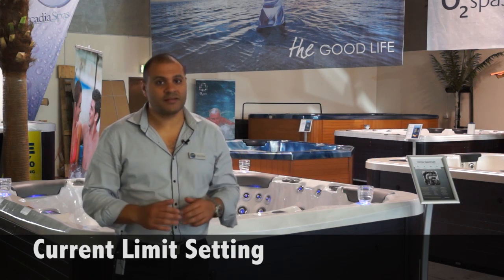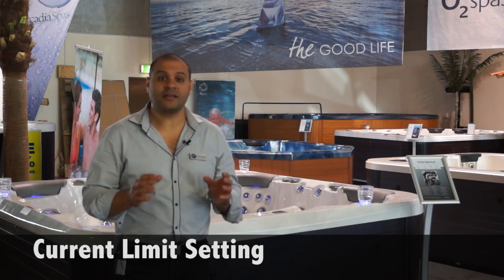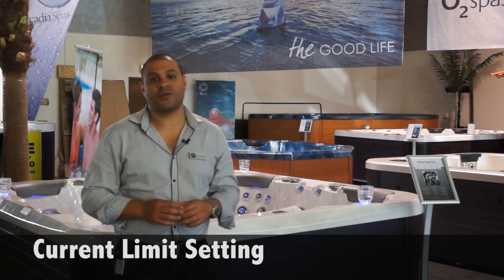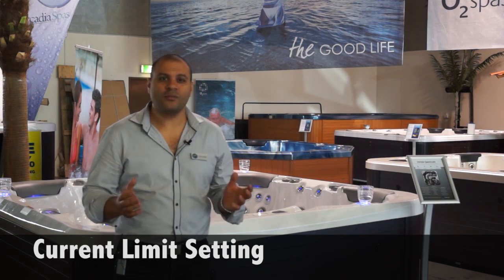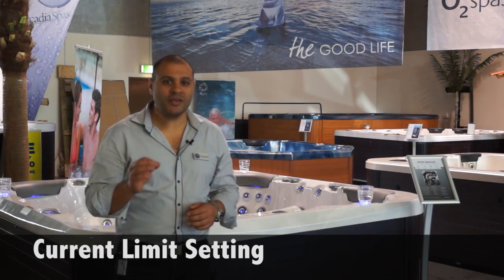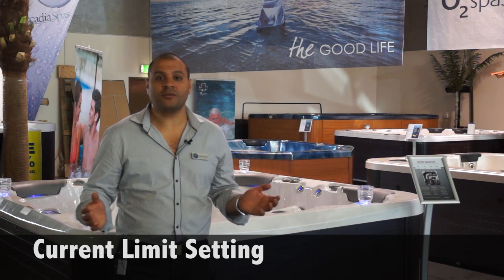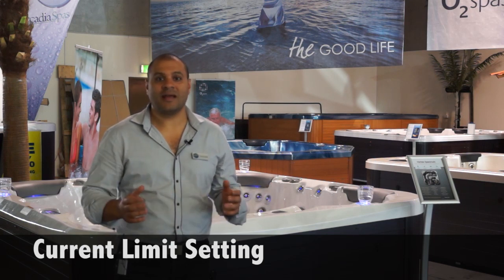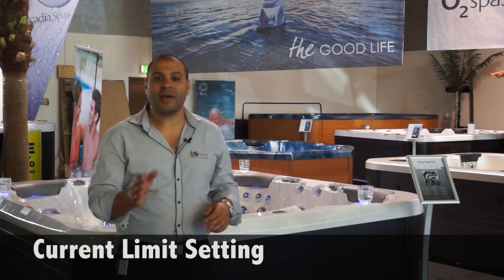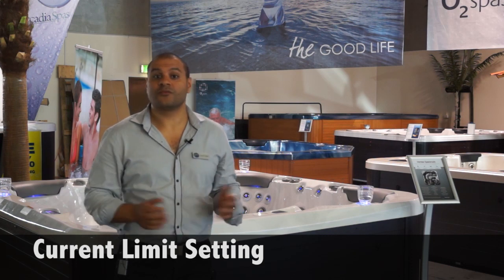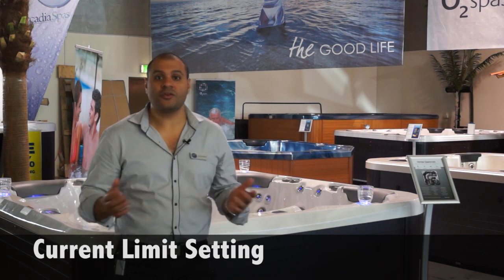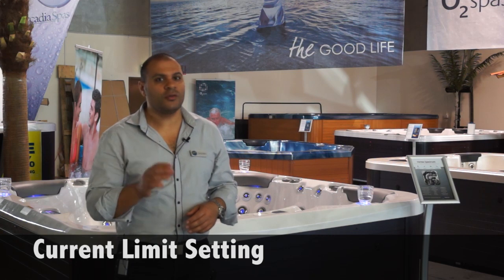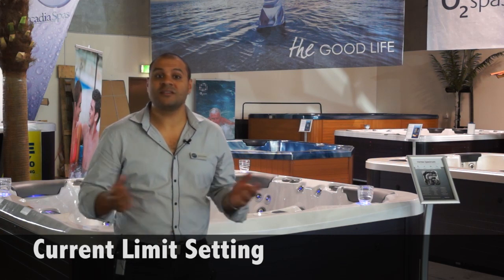In some cases, you may have purchased a particular spa but have less than the recommended power. The great thing with the Vortex controller is this can be adjusted all from the touchpad menu, allowing your spa to run at the most optimum level with the power that you have available. For example, you may have purchased a 32 amp spa but find that you only have 20 amps available. This is not a problem.